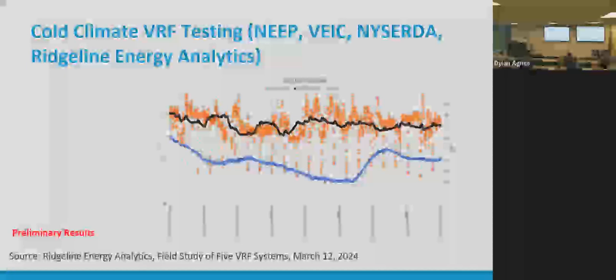All right, I'm going to breeze through these, but this is just some very cold climates that had metered load and input energy and actually quantified COP out in the field. This is a NEEP, Northeastern Energy Efficiency Partnerships, Ridgeline, a bunch of people partnered on it, but they tested a bunch of commercial VRF systems in the field. This is outside air temperature, gets to just under 10, so pretty cold for the whole day. COP is just kind of hovering around 3.5 to 4, average of like 3.5 on the day.